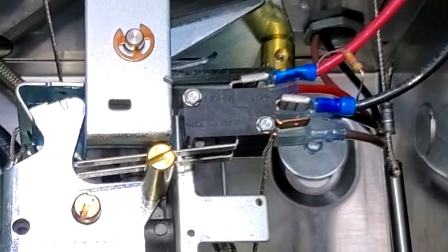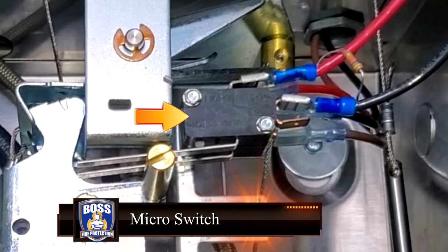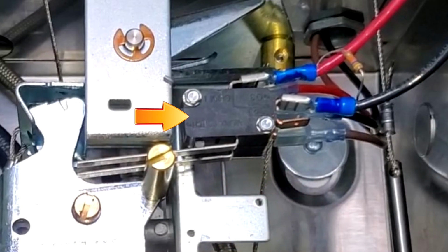The next component is the micro switch. The micro switch ties into the electrical breaker to shut off all electrical supply under the associated vent hoods and fresh air makeup. This small device plays an important role in the system by eliminating any additional fuel to the fire. Once triggered, this device also sets off your fire alarm system, notifying the fire department to respond.